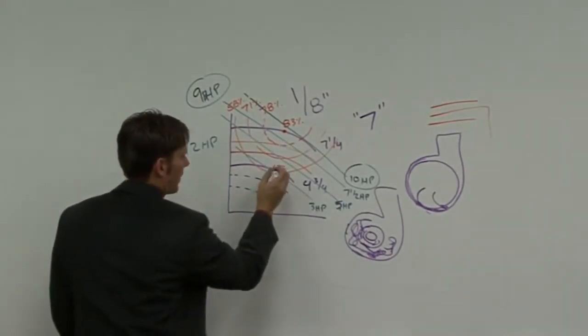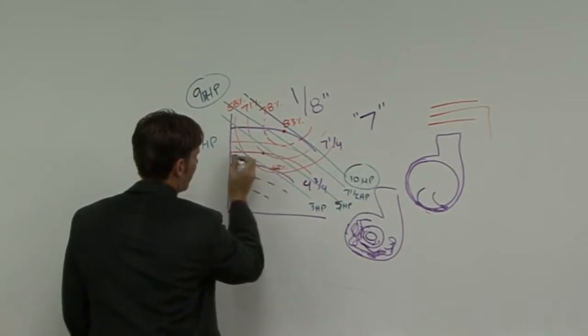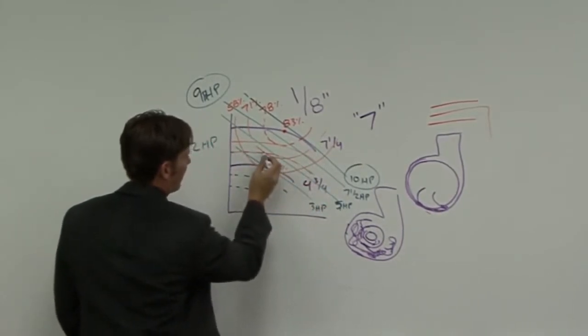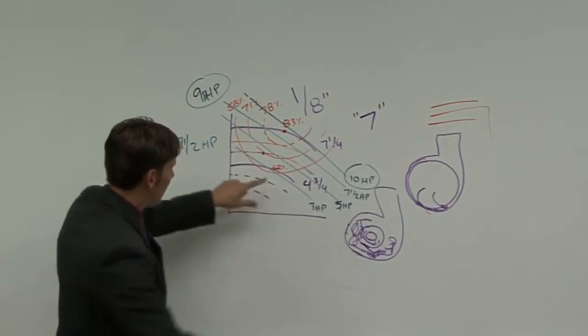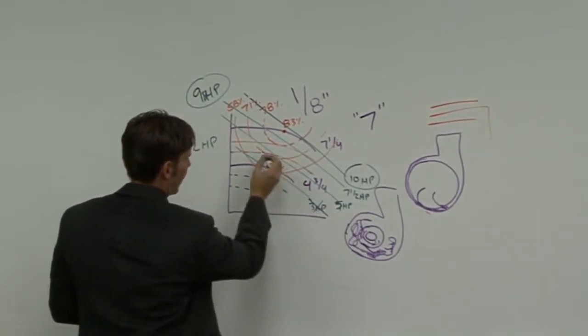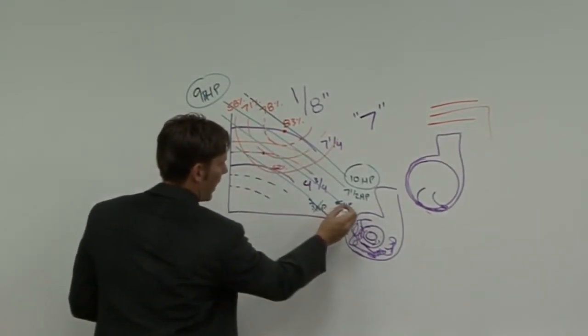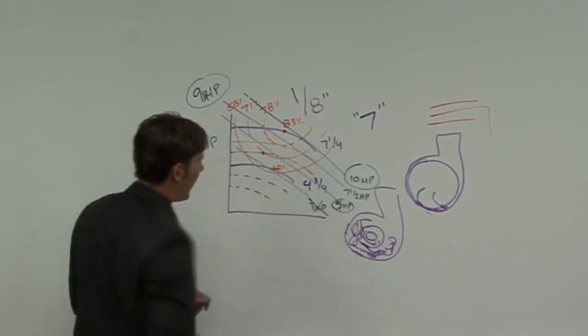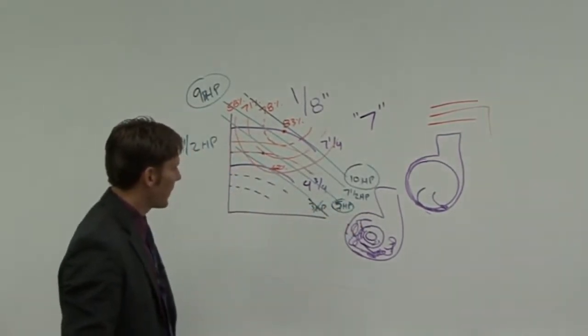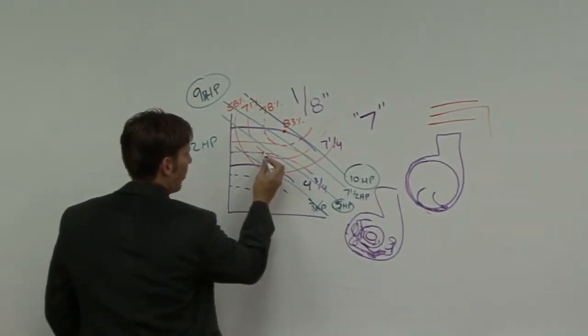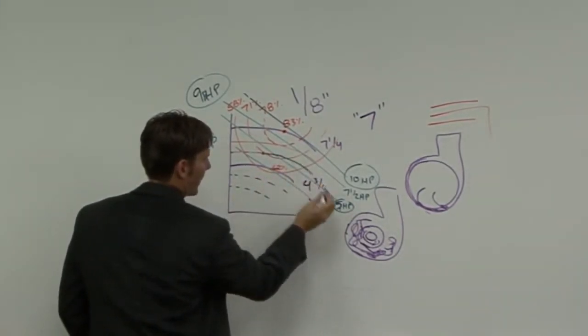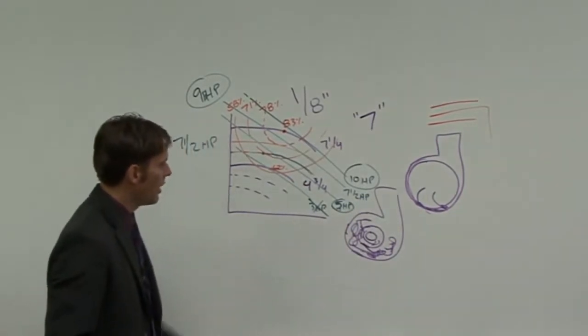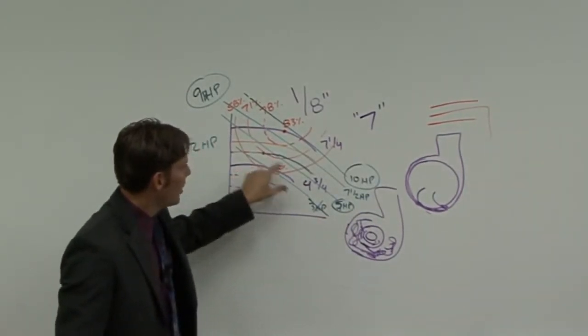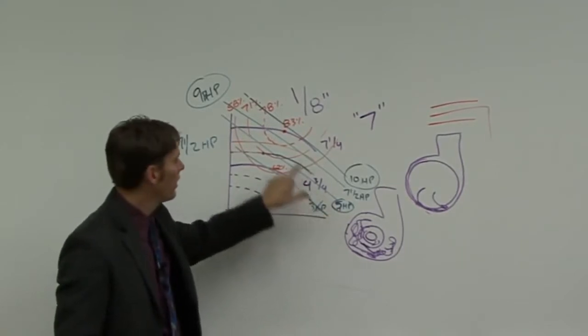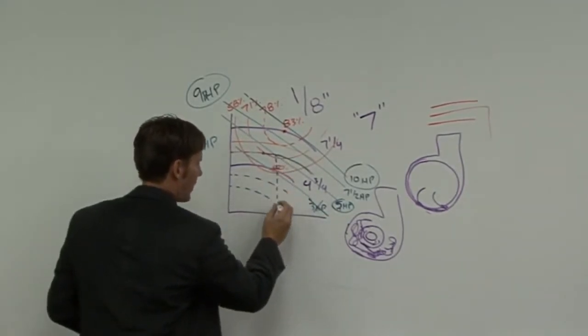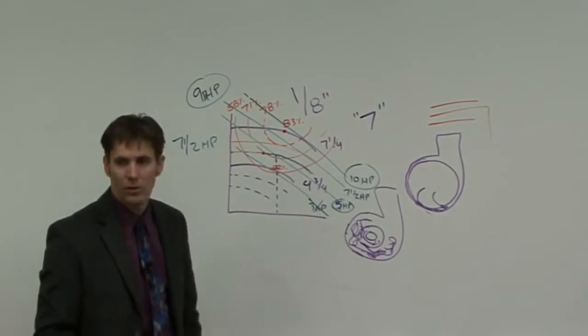If I'm operating way down here, on this curve that's being drawn right here, then I don't want to use a 3 horsepower because I would overload that. But I could use a 5 horsepower. A 5 horsepower looks pretty good. But at some point, I cross that 5 horsepower and I start to approach my 7.5 horsepower. So this pump curve will overload a 5 horsepower motor at a certain flow rate. Once we hit a certain flow rate, then we're going to start to overload that motor.